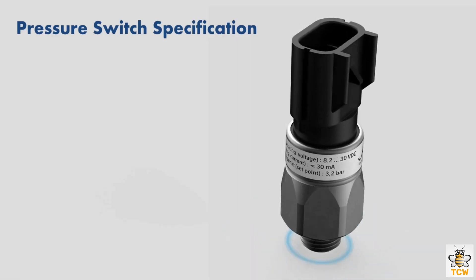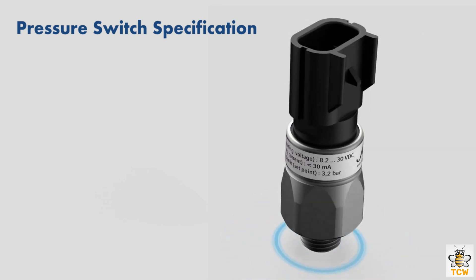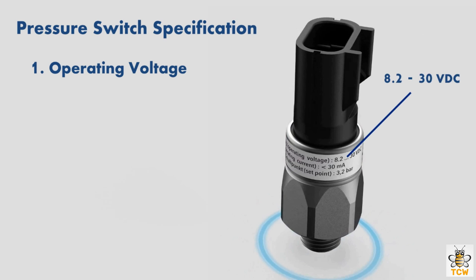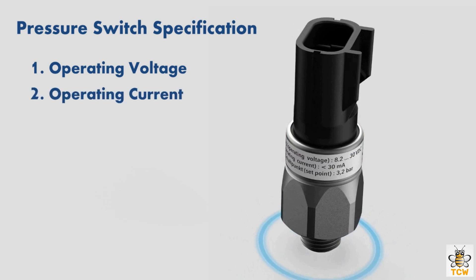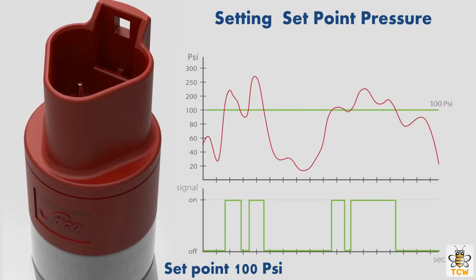In order to function properly, there are several specifications to consider on a pressure switch. The first is the operating voltage — match the type and value of the voltage on the pressure switch with the voltage used on the cable. The second is the operating current — make sure the operating current specification can handle the current flowing in the cable. The third is set point pressure, which is the pressure at which the pressure switch will be activated. In most pressure switches, the set point pressure can be slightly adjusted within a certain range using a screw inside the pressure switch.